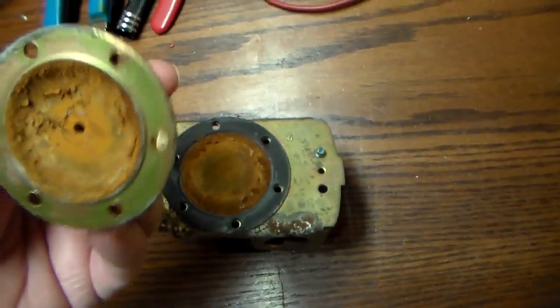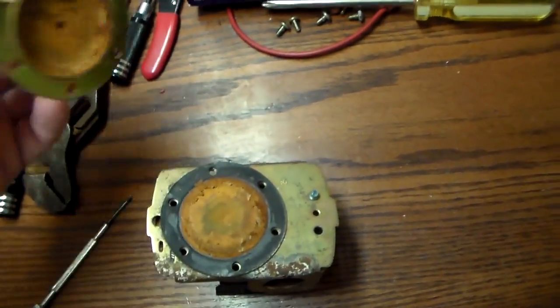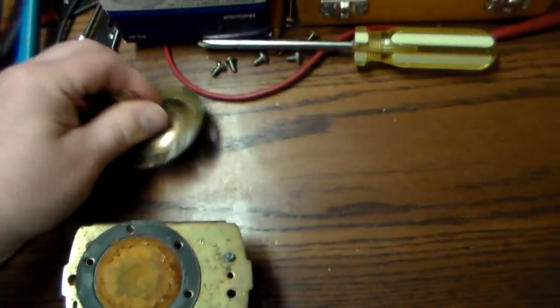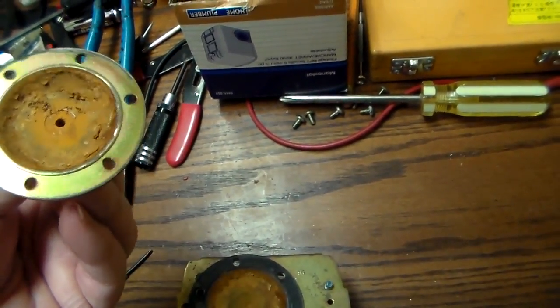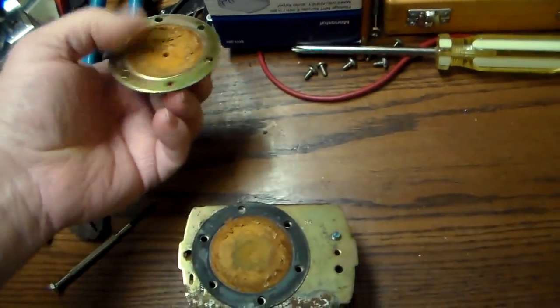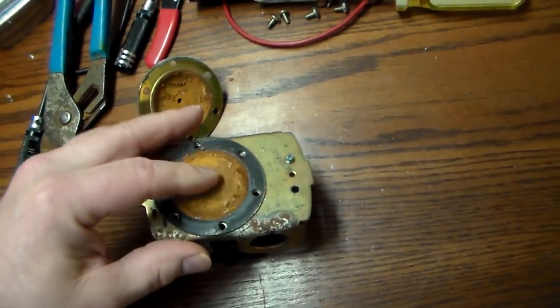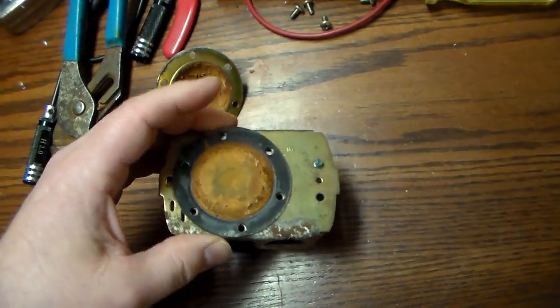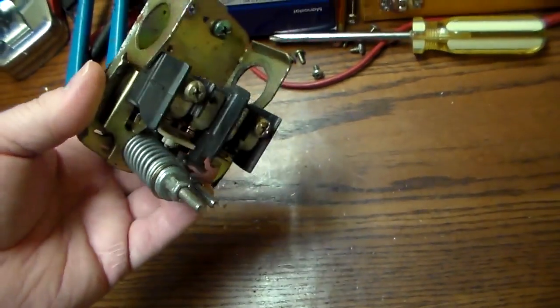You take the diaphragm out, you take this out and you clean it up in the sink with some dishwashing liquid and maybe even a bit of emery cloth or something like that to scrape the rust off. Then you put it back in and it'll probably work for a few more years.